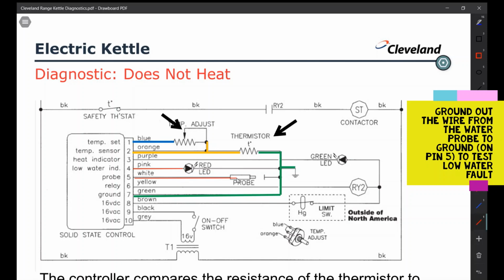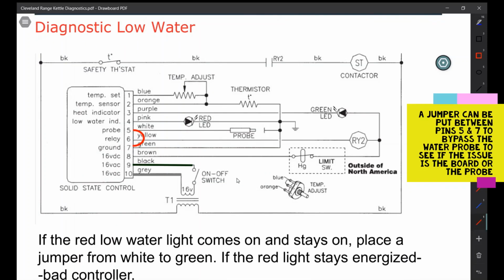The white wire can be removed from the water probe and can be grounded. If the red LED comes off, there's an issue with the water probe. If the red LED stays on, there's an issue with the controller or the white wire from the water probe. Put a jumper between pins 5 and 7 to rule out the board, to rule out a bad probe wire. Okay, so if you go 5 to 7 and your red LED stays on, you have a bad board. If it comes off, you have a bad probe or a bad probe wire.